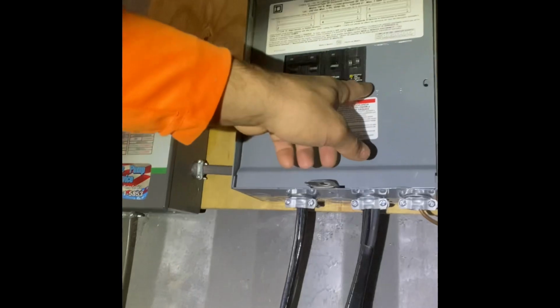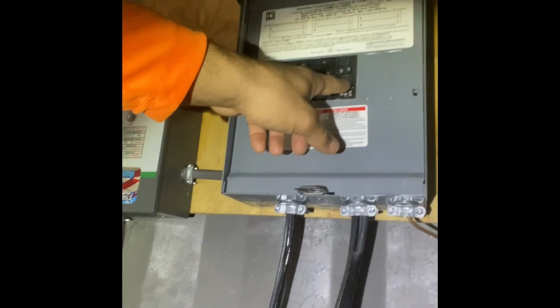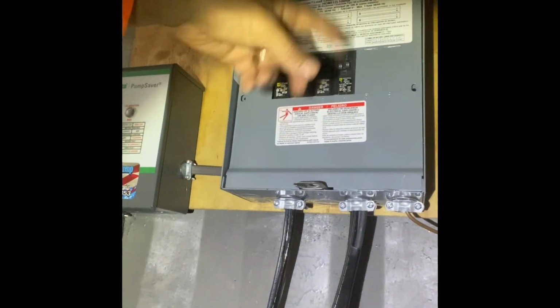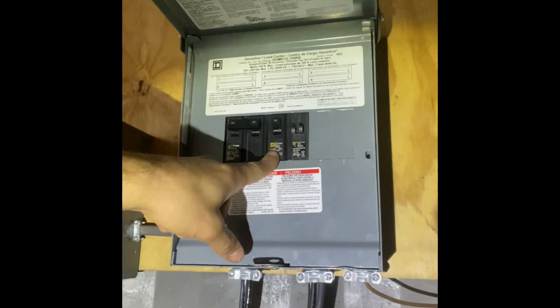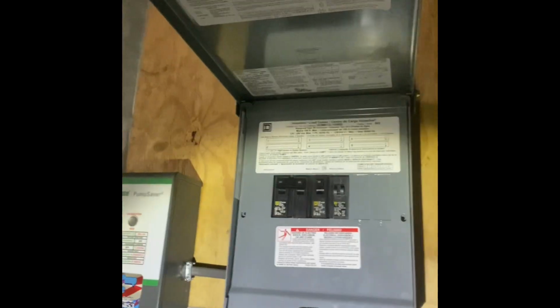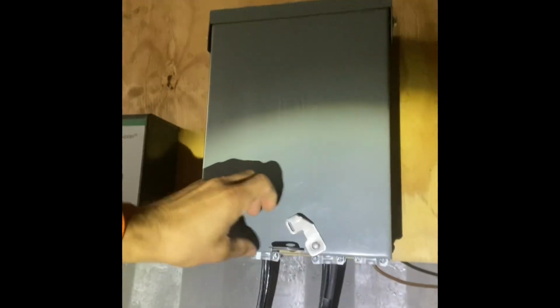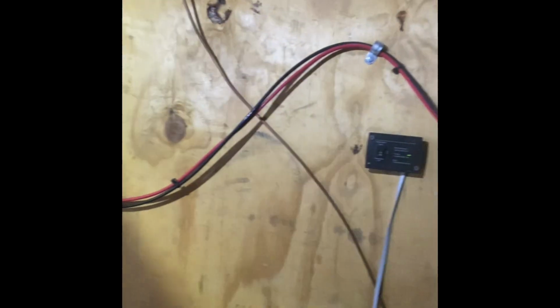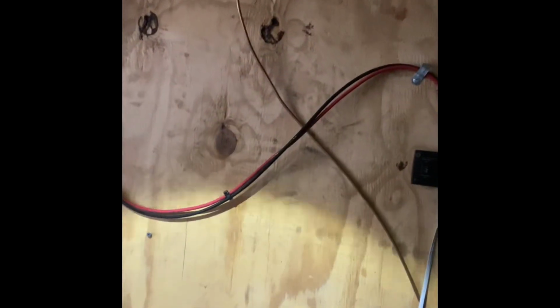I have a couple extra slots here, a pigtail slot for future use of something else, not being used. Then a 30 amp circuit breaker that's currently servicing the RV we're staying in. It's more than enough power, 3,200 watts is more than enough to service an RV. So there you have it. That's also 6 gauge coming into the circuit breaker.